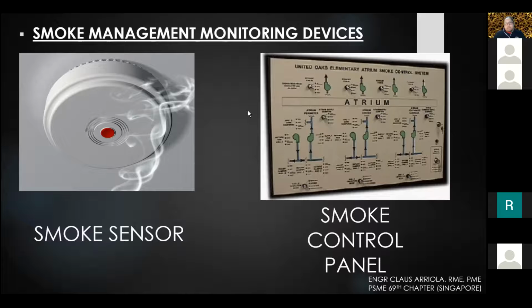But mind you guys, with the smoke sensor, you need to carefully design its location. If it's too high, it's very difficult to maintain. When it gets dusty, sometimes it makes a false alarm. So you need to maintain smoke sensors every 3 months. When it gets dusty, it's very hard to tell whether it's a real fire or a false alarm. Then it creates a nuisance to your occupants.